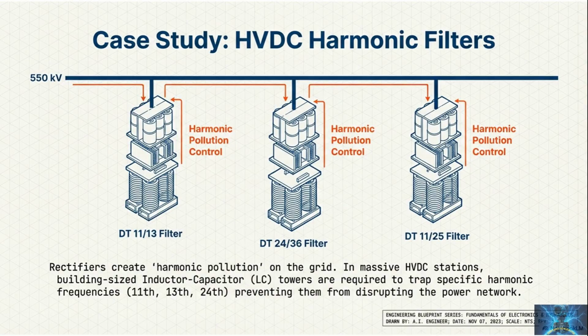Case study: high-voltage direct current harmonic filters. Rectifiers do not just make direct current, they also create harmonic pollution on the alternating current grid. Harmonics are unwanted frequency components that can heat equipment and distort system waveforms. In high-voltage direct current stations, you'll see massive inductor capacitor filter banks built to trap specific harmonic frequencies. The point is simple. When power scales up, cleanup hardware scales up too.